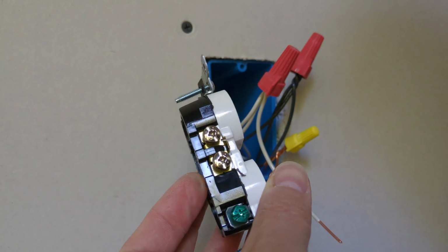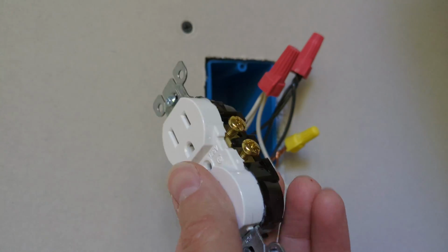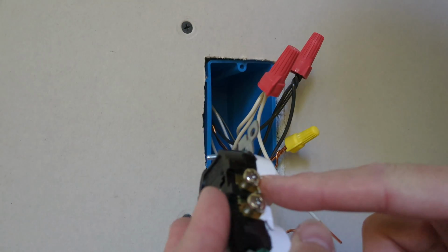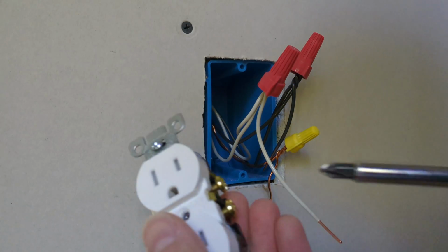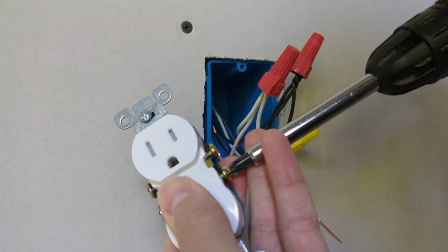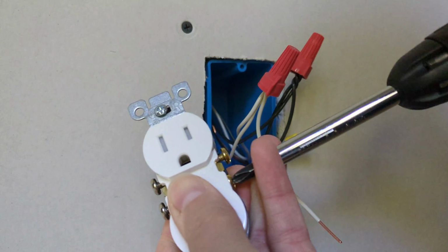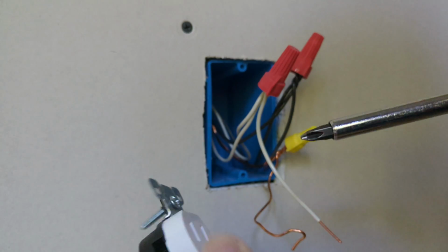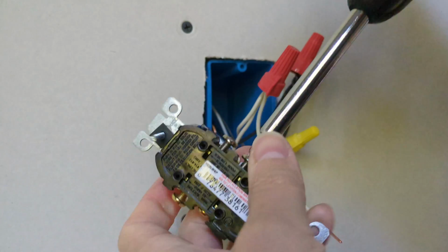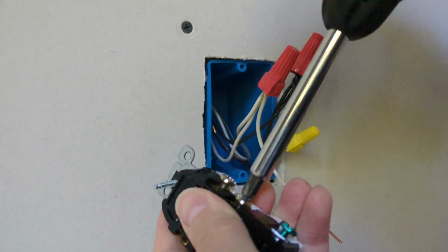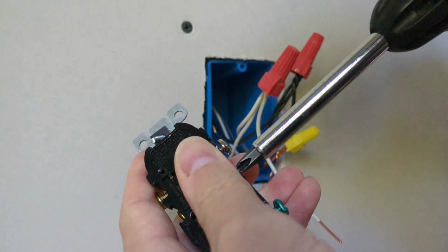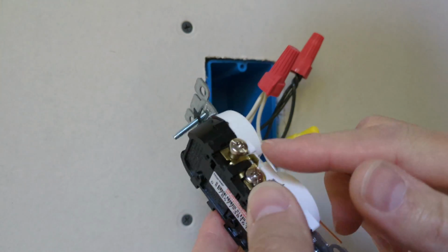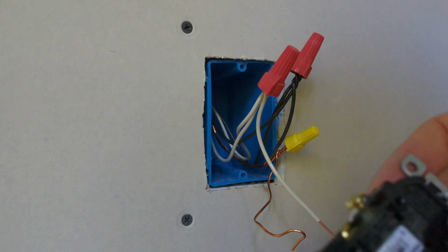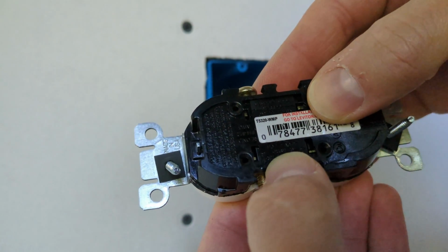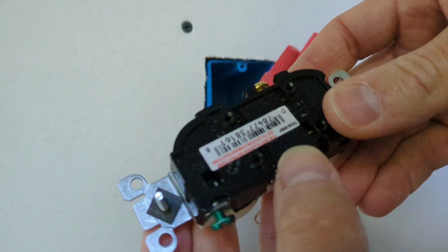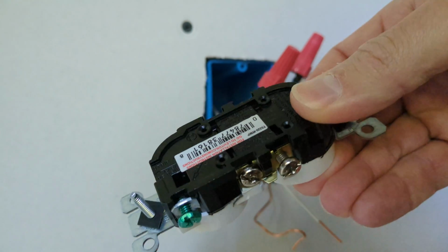Now we'll get our outlet ready. That's just a 15 amp outlet in a mudroom. So I'm only going to connect wires, let's say, to the top screw terminals. I'll tighten down what will be the unused terminals. Don't want those sticking out. So you have three wires to connect: ground, neutral, and hot. If you're not sure, it says right here on the back. Says hot for the black or hot wire, and here it says white for connecting the neutral wire.